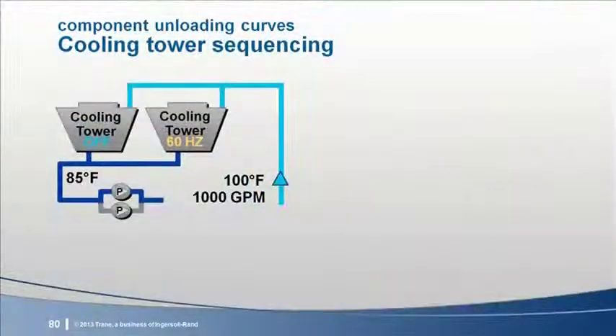First up, cooling towers. Here's an example of a typical two-chiller, two-cooling tower condenser water system operating with one chiller and one tower near design condition. Note that it's designed with an energy and installed cost optimized 15-degree delta T, about 2 GPM per ton. At design conditions, the cooling tower fan operates at the full fan speed of 60 Hertz and draws 15 kW.